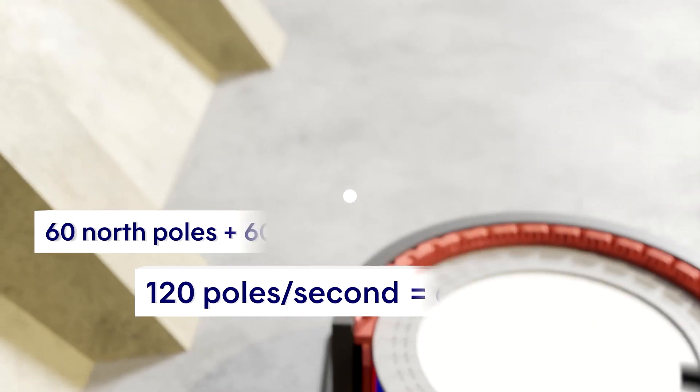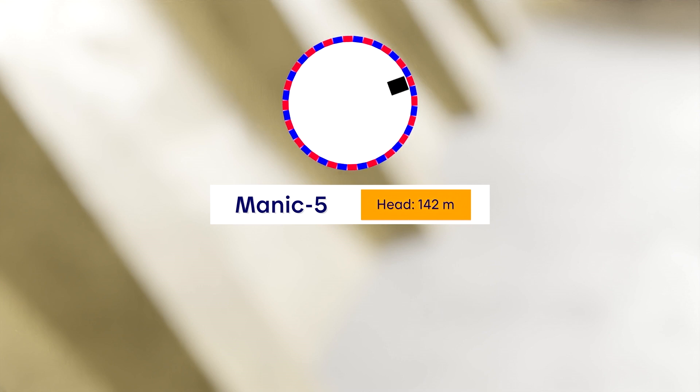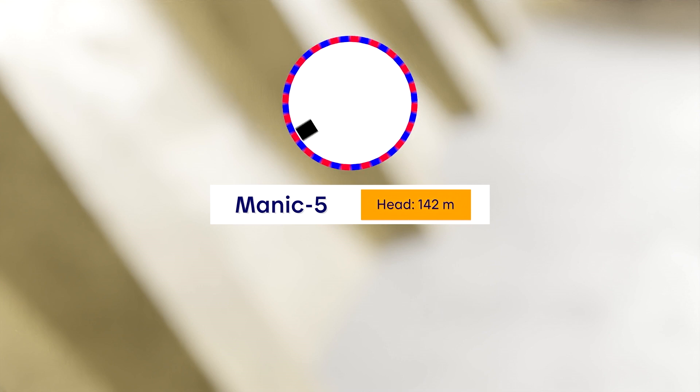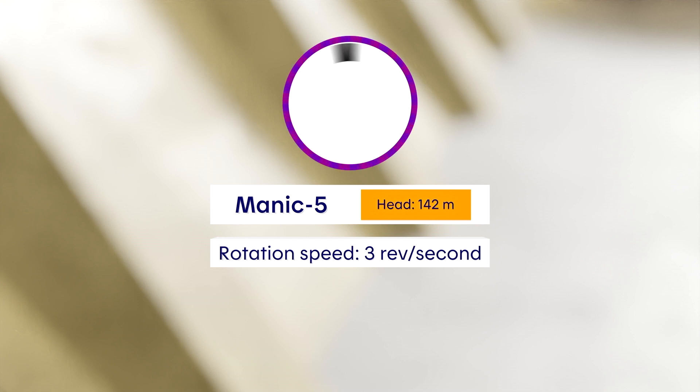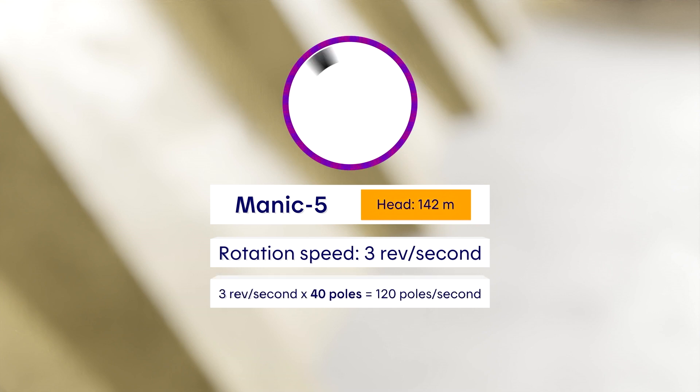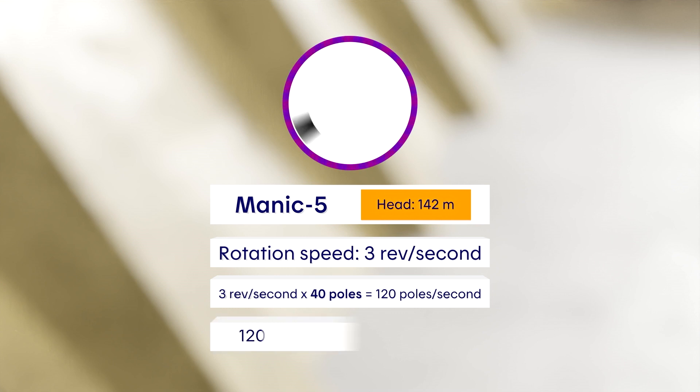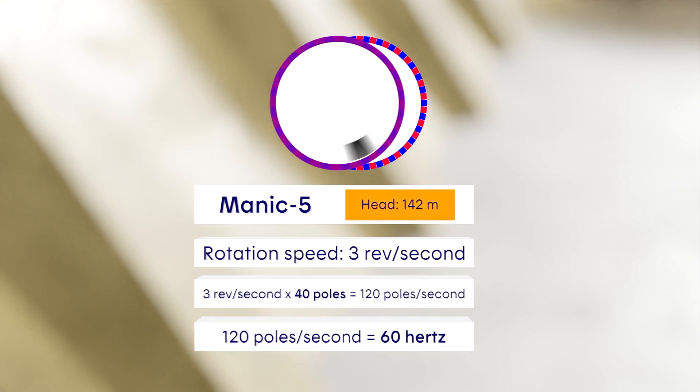Let's look at a concrete example involving a real generating station. At Manic 5, the hydraulic head is high, so the rotor spins at a high speed, reaching 3 revolutions per second. At 3 revolutions per second, how many poles does the rotor need to reach a frequency of 60 hertz? Remember that 120 poles per second is equivalent to 60 hertz. The rotor makes 3 revolutions per second, so it takes 40 poles to reach 120 poles per second, since 120 poles per second is 60 hertz.